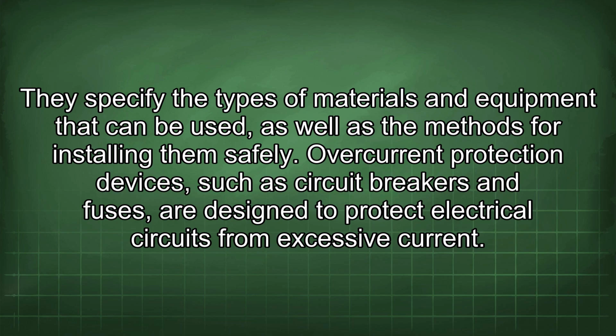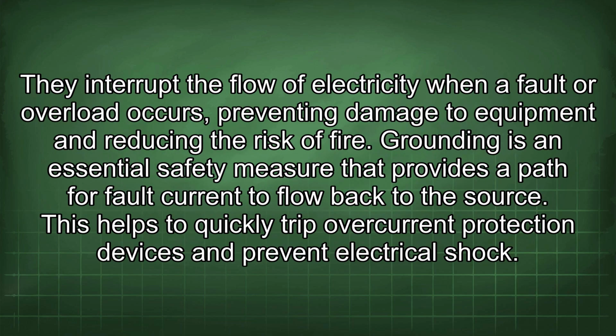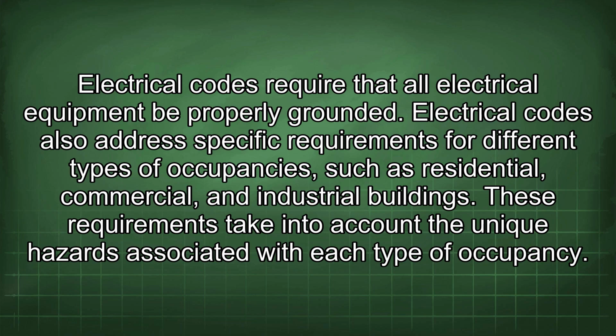safely. Overcurrent protection devices, such as circuit breakers and fuses, are designed to protect electrical circuits from excessive current. They interrupt the flow of electricity when a fault or overload occurs, preventing damage to equipment and reducing the risk of fire. Grounding is an essential safety measure that provides a path for fault current to flow back to the source. This helps to quickly trip overcurrent protection devices and prevent electrical shock. Electrical codes require that all electrical equipment be properly grounded.